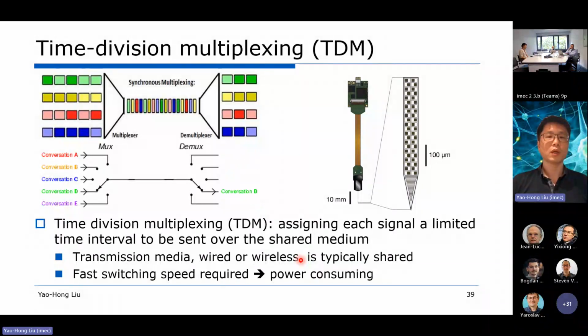This is a standard approach. By using this time multiplexing, we can reduce the number of wires. Again, I want to use the NeuroPixels as an example. NeuroPixels has a total of 384 recording channels, and each channel has more than 10 bits. If we try to wire all of the ADC bits out, it's going to be thousands of wires, which is again not very practical. So actually, NeuroPixels performs time multiplexing, so the output is only a few wires, making the system very compact and more suitable for potential implant use.